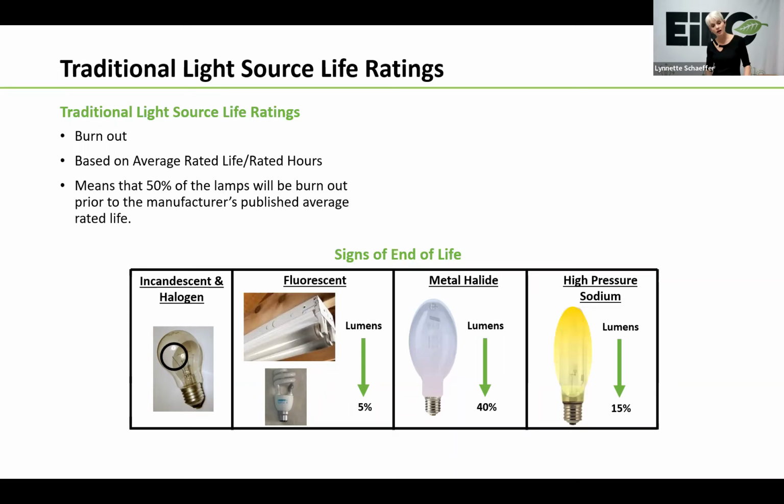Then the next day it'll turn back on. Kind of a maintenance nightmare because it's really hard to troubleshoot when you're not out there and know exactly what lamp is having that problem. Now, high pressure sodiums also lose light as they age. Not quite as bad as metal halides, but they still lose about 15% lumen output.